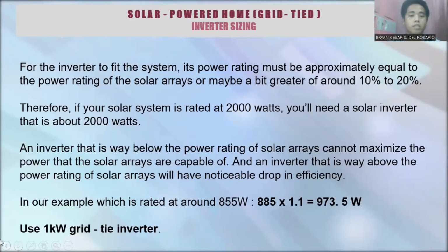So therefore, if your solar system is rated at 2,000 watts, you'll need a solar inverter that is about 2,000 watts. Kung yung solar system natin ay nag-rate ng 2,000 watts, ang kailangan rin nating solar inverter ay 2,000 watts rin. An inverter that is way below the power rating of solar arrays cannot maximize the power that the solar arrays are capable of. And an inverter that is way above the power rating of solar arrays will have a noticeable drop in efficiency. Kailangan talaga is saktong-sakto lang yung gagamitin natin.